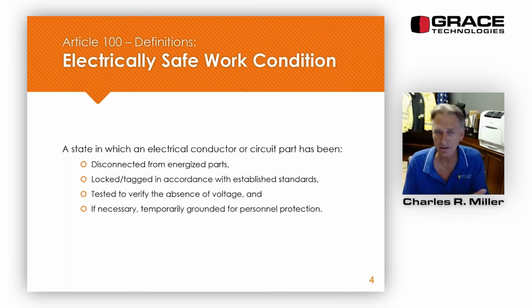All right, here's the definition of electrically safe work condition. It's a state in which electrical conductors and circuit parts have been, first of all, disconnected from energized parts. They've been locked and tagged in accordance with established standards. A lot of industrial factories and plants, and I teach in quite a few plants here and there, if a plant does nothing else, typically they at least have a lockout tagout program. But lockout tagout is only one step in establishing and verifying an electrically safe work condition. The third part is testing to verify the absence of voltage, to make sure there is no voltage there, and we have specific steps in testing for the absence of voltage. And the last one, if necessary, is using temporary electrical safety grounds for personal protection.